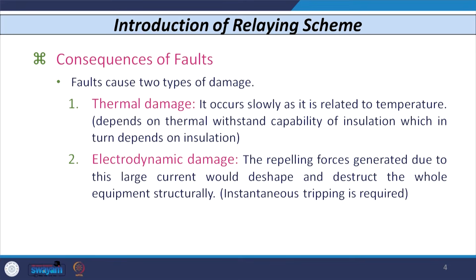The second type of damage that occurs is known as electrodynamic damage. In this case the magnitude of current is very high, roughly 10 times or 15 times or 20 times the full load current or rated current. The repelling forces generated are such that they are going to deshape and sometimes destroy the whole equipment structurally. So, your equipment is going to get damaged structure-wise. As the magnitude of current is very high, 10 times or 20 times, instantaneous tripping is required, whereas in the earlier case, thermal damage, instantaneous tripping is not required, because there is no immediate harm as far as insulation is concerned.